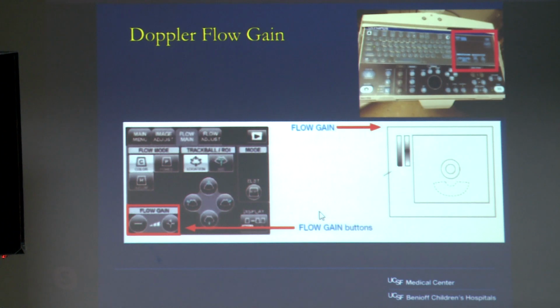Then within the Doppler, one can change the gain to adjust the signal strength. If the signal is not very audible, it doesn't mean that there isn't flow. It may be that the flow is slow, and if we increase the gain, we may be able to pick up that Doppler flow. So it's important when you don't have flow to make sure that you change the gain to ensure that it's not an issue with not being able to detect it.